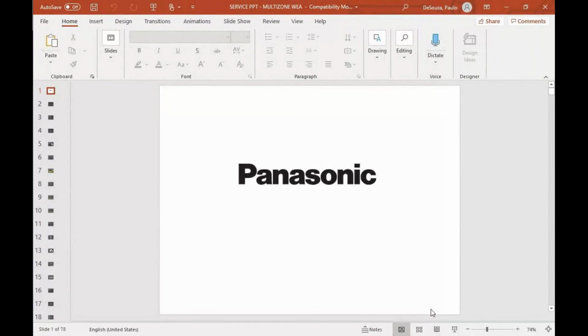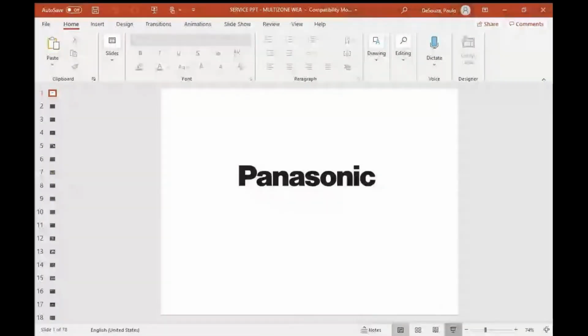Okay. So transducers are available as we speak, but not on small units. Transducers are on our VRF systems. So basically what you do, you hook up your laptop and you can see everything there, no problem. You can see your running amps, you can see your pressures, you can see your compressor frequency and all that kind of thing. If we start putting transducers, bells and whistles on this small unit, it's going to cost so much.